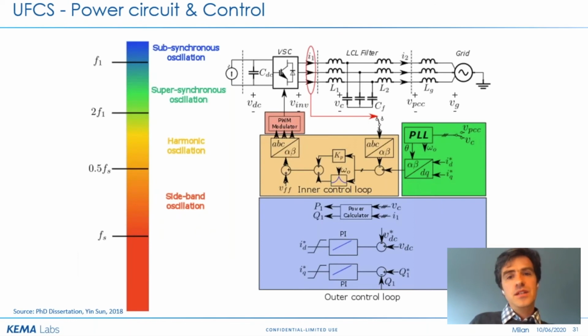If you look at what these power electronics mean to the frequencies of the grid, I mentioned that in the beginning, we are now looking at different frequency components instead of just the fundamental frequency. You will have to, and you can see the color coding between the blocks of the control and on the left, what it means for the frequency component in the grid spectrum. You will need to take into account more aspects and look at different frequency components in your grid study to see how you integrate such charging systems into your grid, especially if they're next to highways, behind long feeders, far away from transformers.